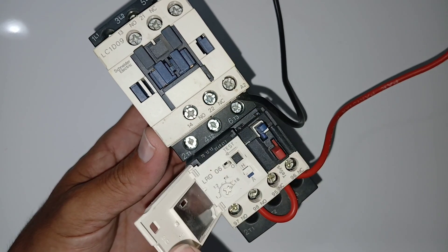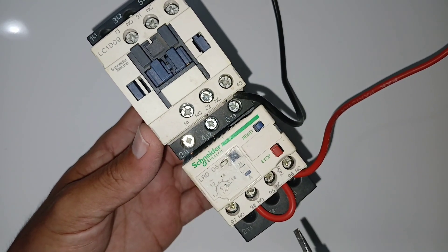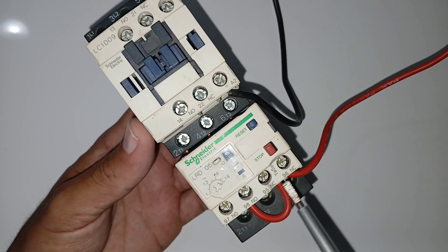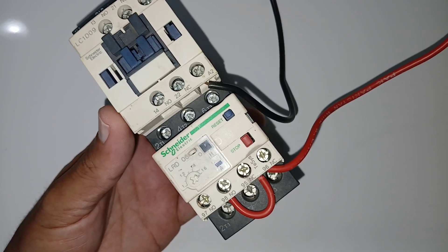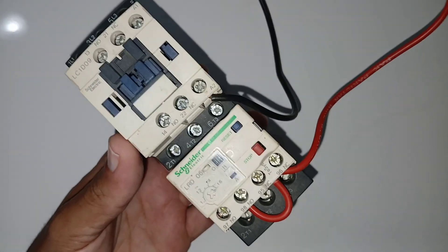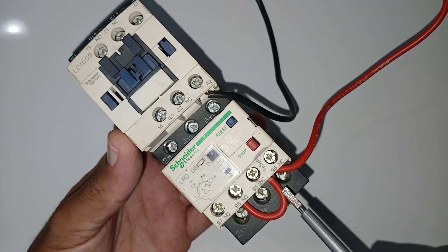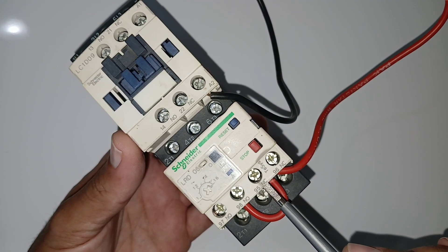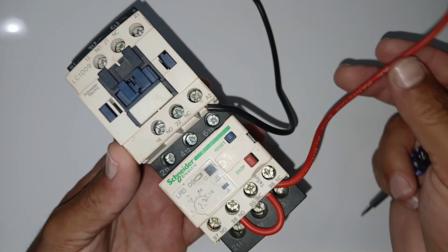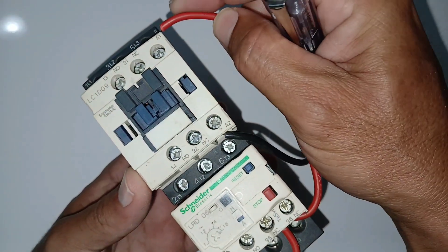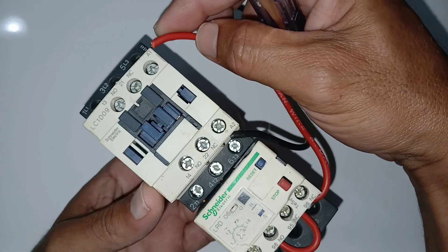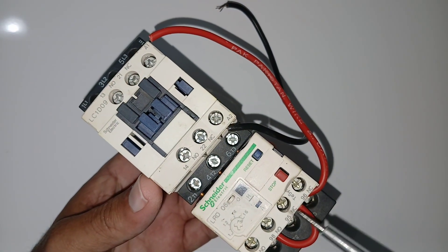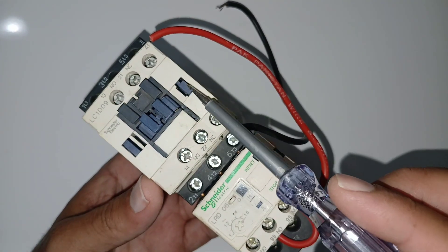so the contactor will stop. So power, no more power will go to the motor. Now you can see the points 97, 98, 95, 96. How do you do connection? You need to give one power to 95, and from 96, you need to take out like that to the A1 point. Clear? Like that. So this power will go, it will get on the contactor.